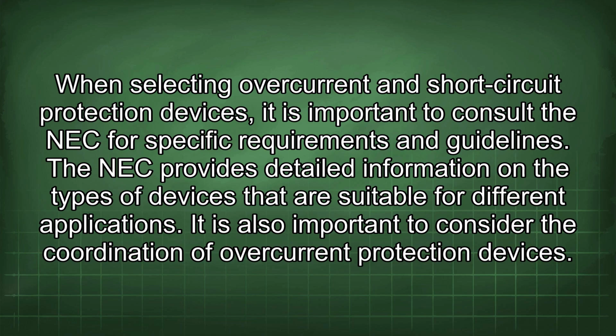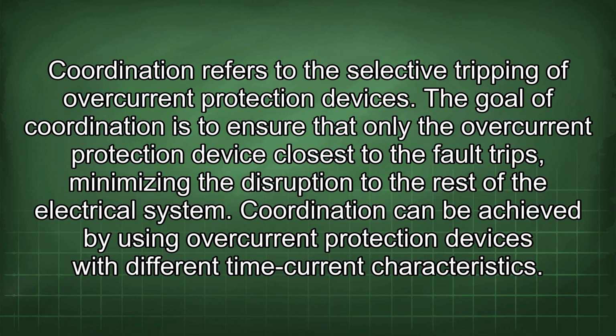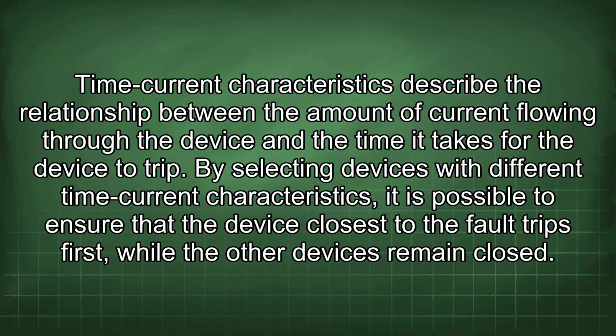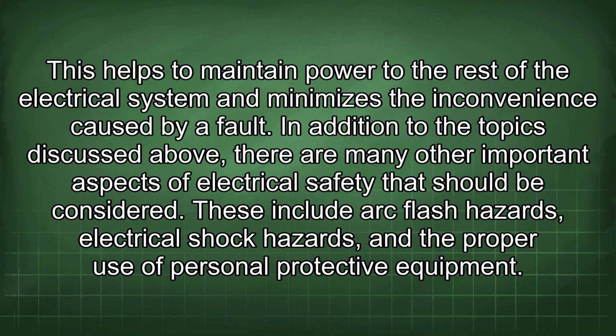It is also important to consider the coordination of overcurrent protection devices. Coordination refers to the selective tripping of overcurrent protection devices. The goal of coordination is to ensure that only the overcurrent protection device closest to the fault trips, minimizing the disruption to the rest of the electrical system. Coordination can be achieved by using overcurrent protection devices with different time current characteristics. Time current characteristics describe the relationship between the amount of current flowing through the device and the time it takes for the device to trip. By selecting devices with different time current characteristics, it is possible to ensure that the device closest to the fault trips first, while the other devices remain closed. This helps to maintain power to the rest of the electrical system and minimizes the inconvenience caused by a fault.